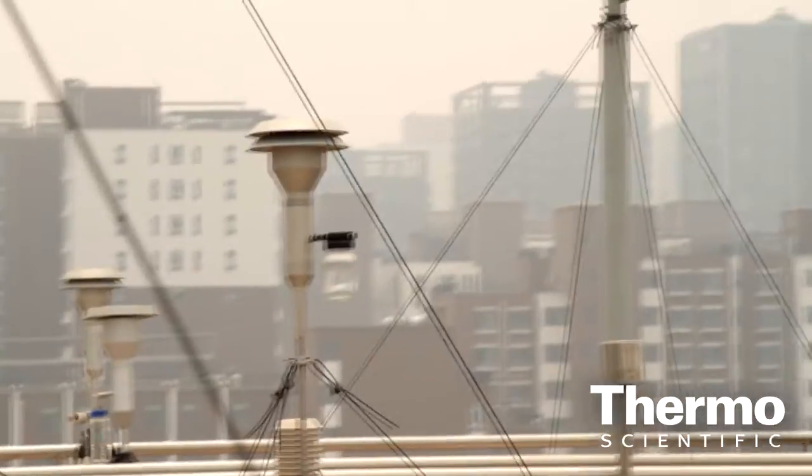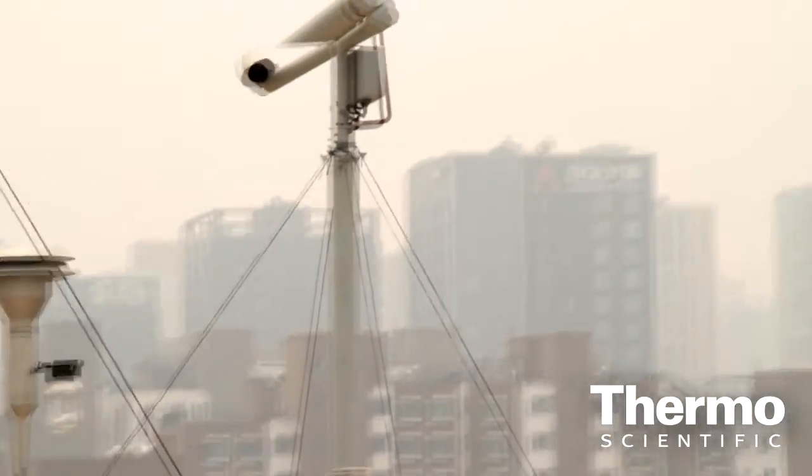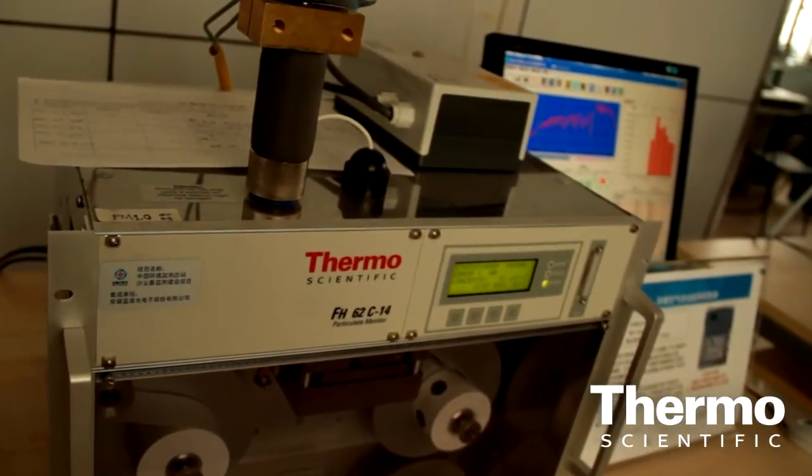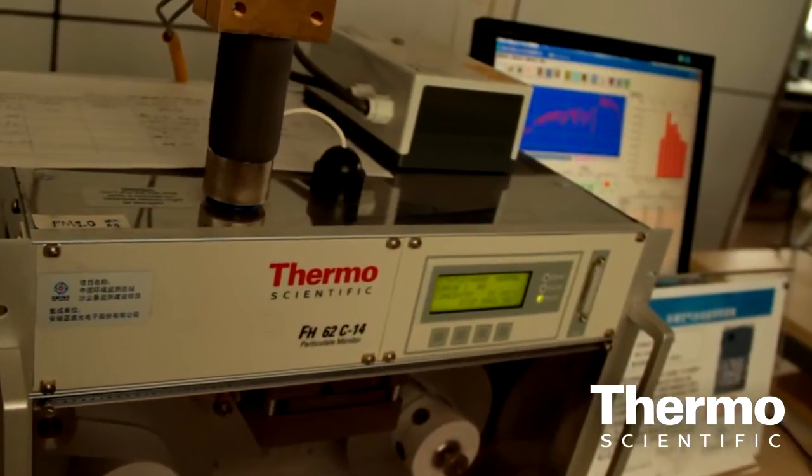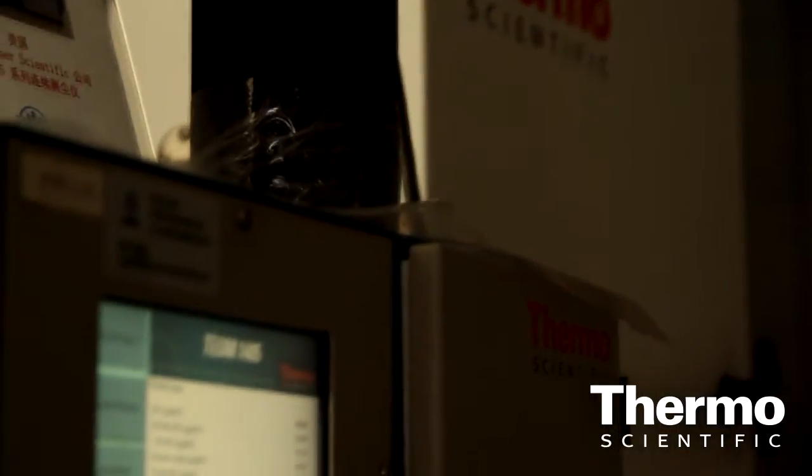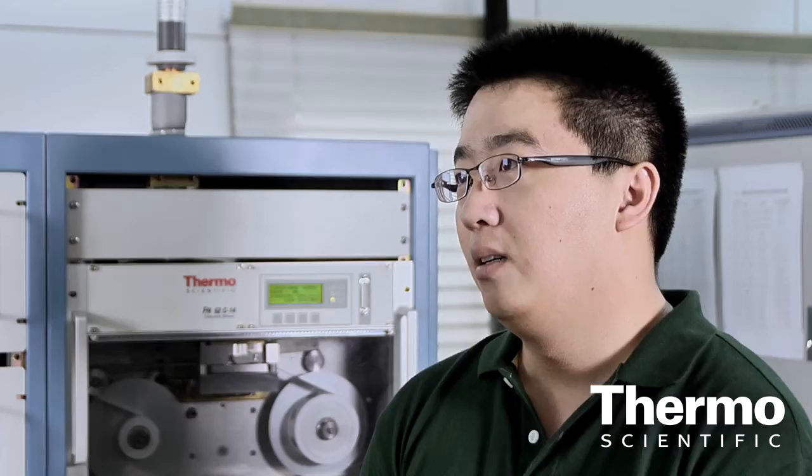Customers select our instruments mainly because of the performance, good quality and much less required maintenance, using particulate matter PM10 as an example. We are the only manufacturer of two continuous methods. One is beta attenuation and the other is tapered element oscillating micro-balance. Customers are satisfied with the small amount of consumables used in our instruments.